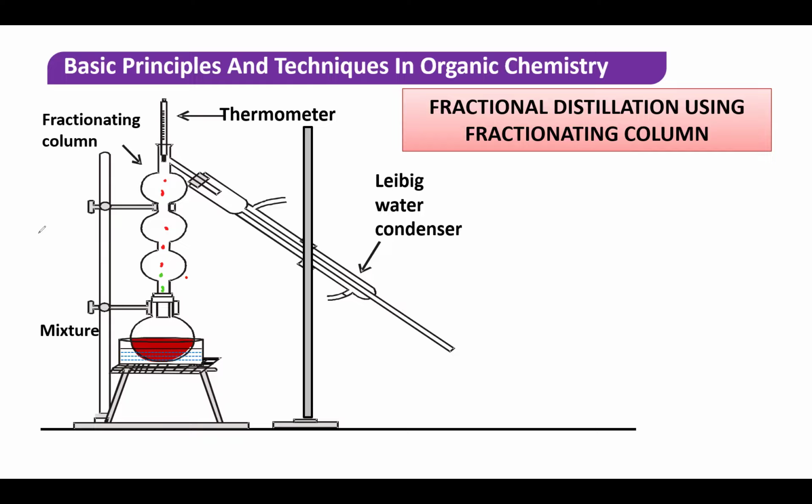So now what is happening? Look here. Which liquid is moving ahead? The red one. Now behind, who was going? Tell me. The green one. But here it is traveling more distance. So from outside, who is cooling it? From outside, air is cooling it. So who will get condensed first? The red one. So the red one will fall down because it will become liquid.